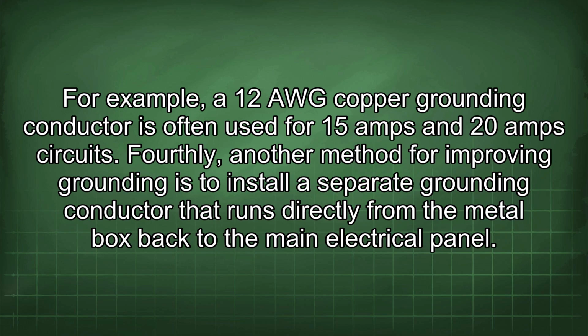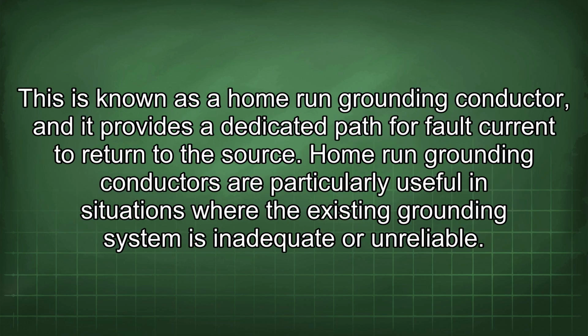Fourthly, another method for improving grounding is to install a separate grounding conductor that runs directly from the metal box back to the main electrical panel. This is known as a home run grounding conductor, and it provides a dedicated path for fault current to return to the source. Home run grounding conductors are particularly useful in situations where the existing grounding system is inadequate or unreliable.